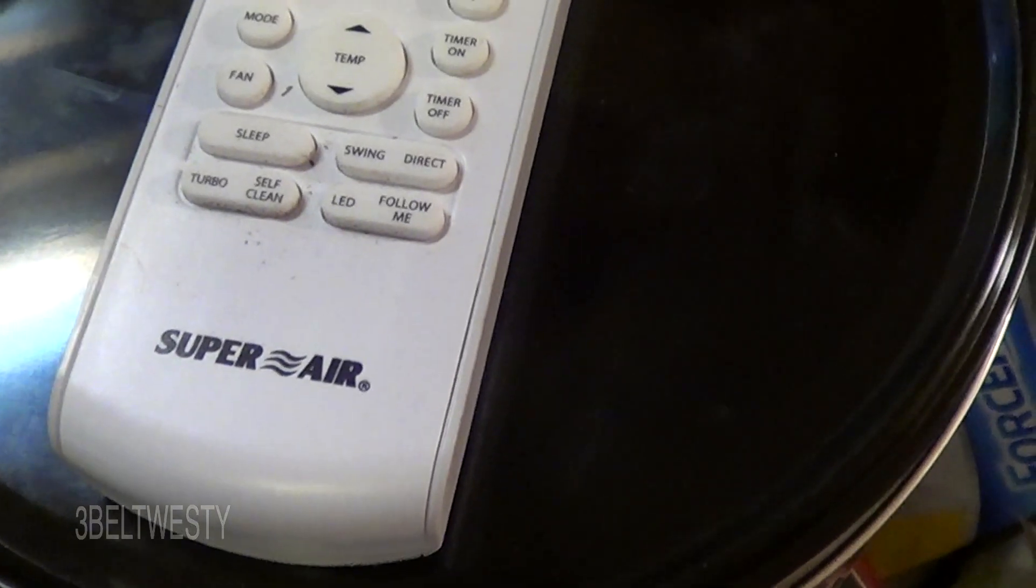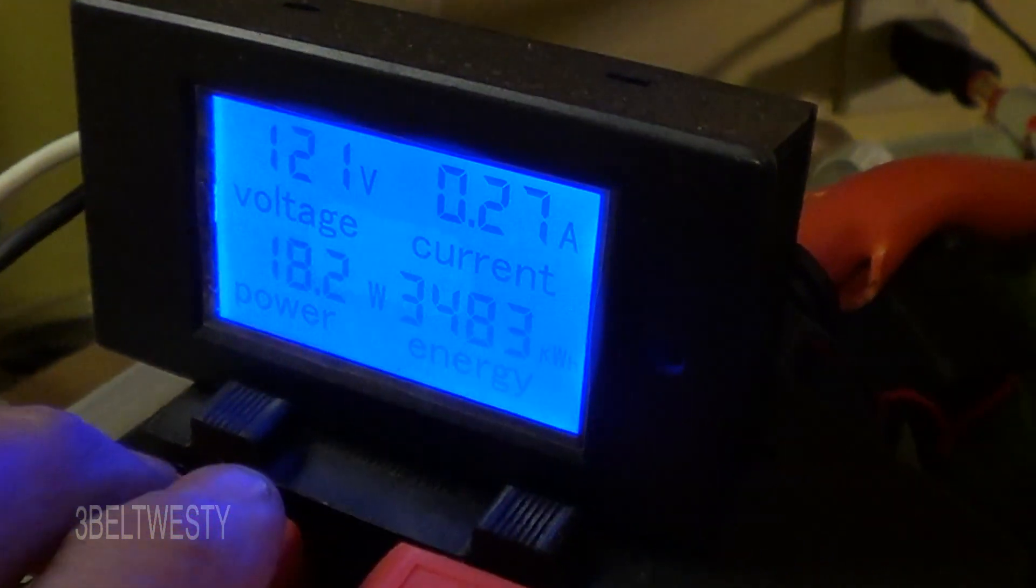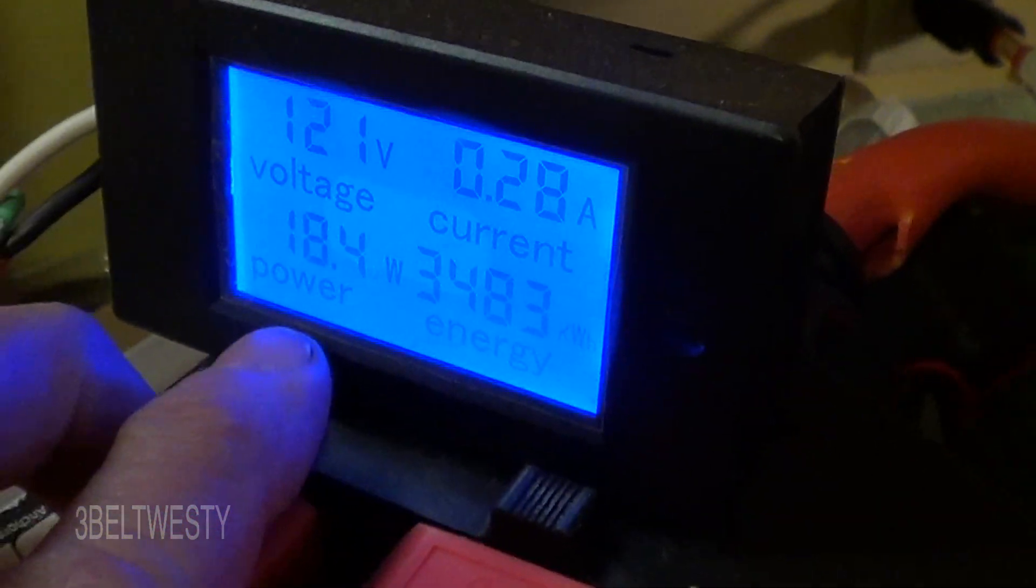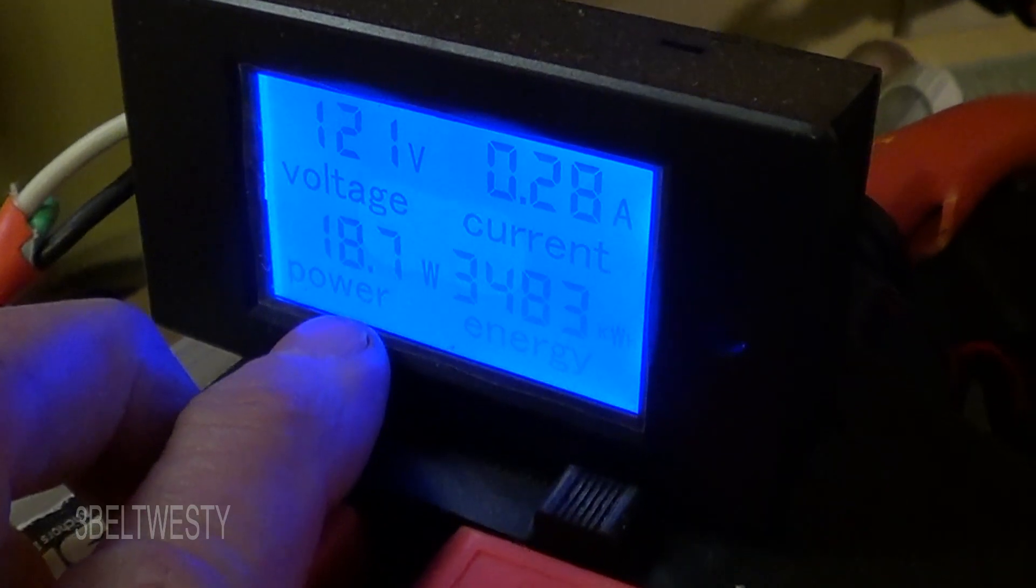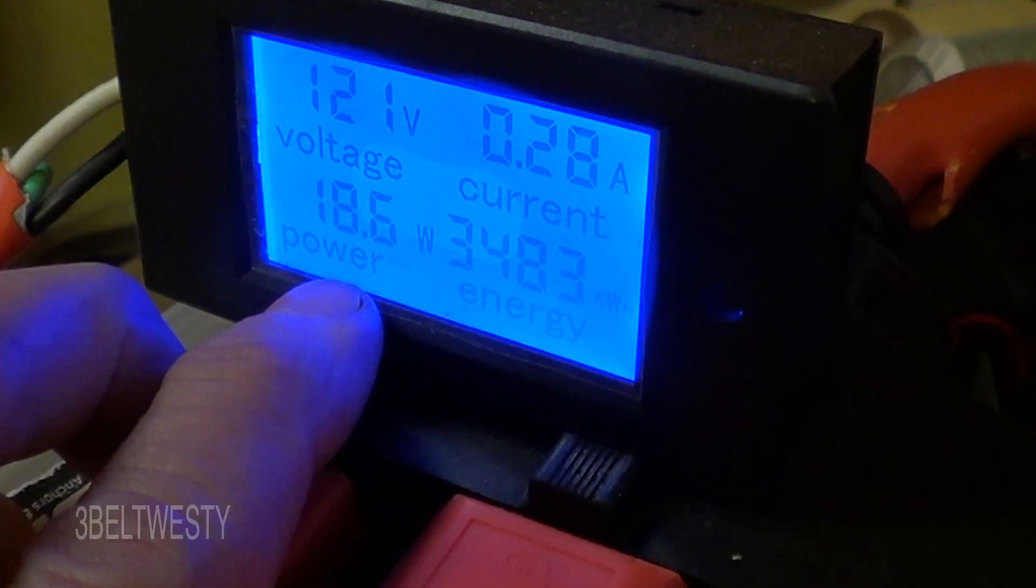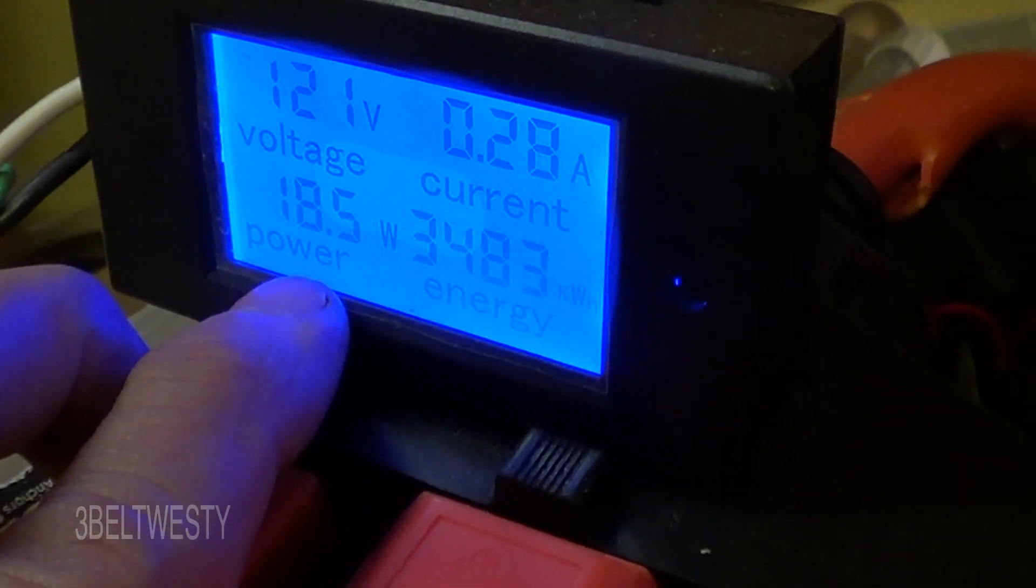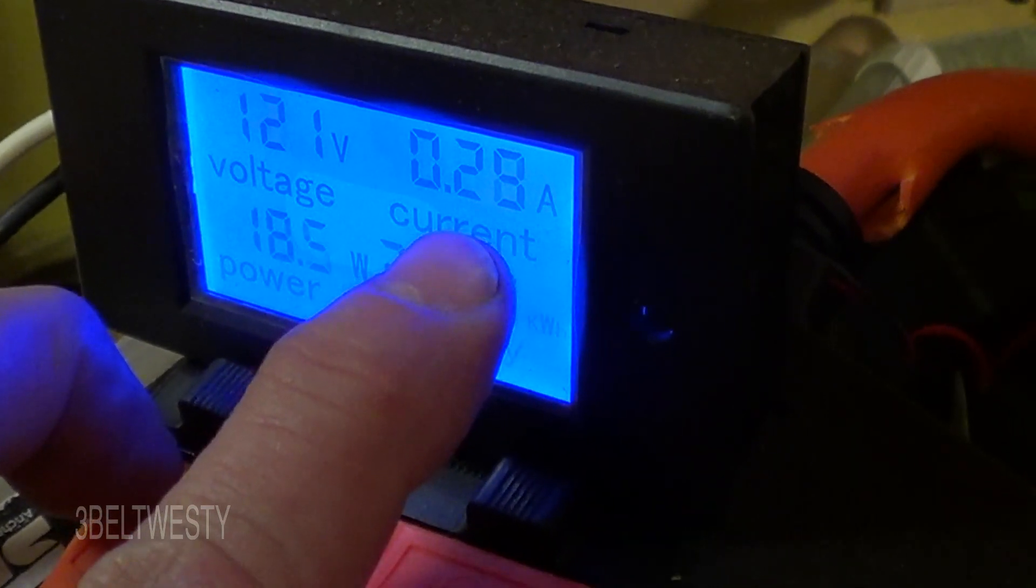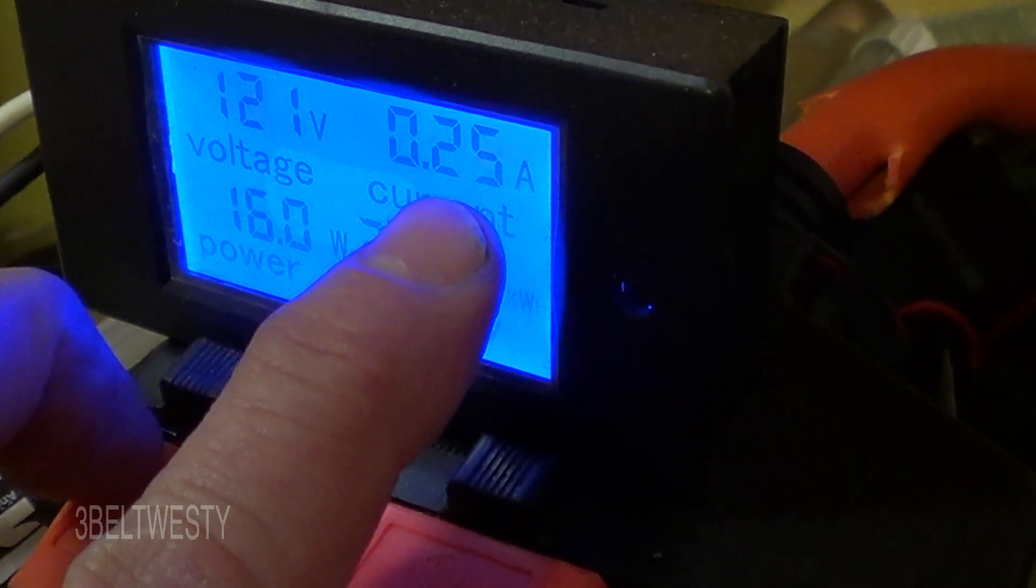Okay, I've got the mini-split turned off, and over here on a power meter I've rigged up, it's always on. Over here it's dancing between, say, 15 to about 18 watts, roughly about a quarter amp, 0.25, 0.28.